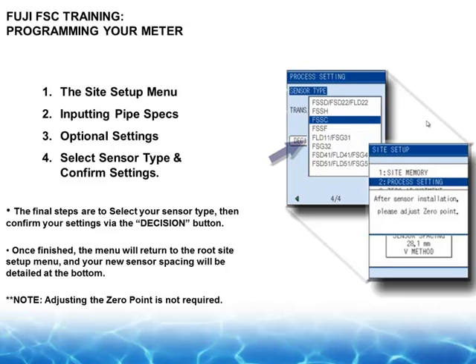So if you're getting a reading that's always 10% high or always 20% high, you probably set the 0. So talk to us. We'll show you how to reset that. As a general rule, the only time you ever set the 0 point is if you're working with flows in the tenths of a foot per second. So for the most part, leave it alone. When that screen pops up, it will give you the sensor spacing. In this case it's metric, but if it was English, it would give you so many inches apart between the transducers, and the method of installation.